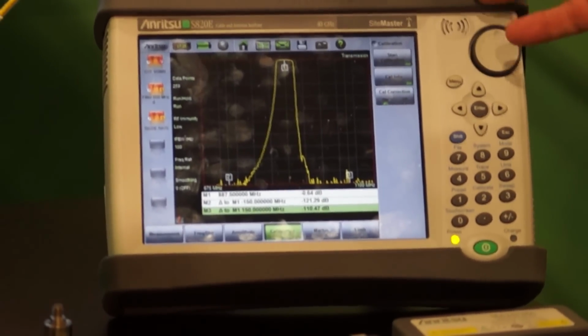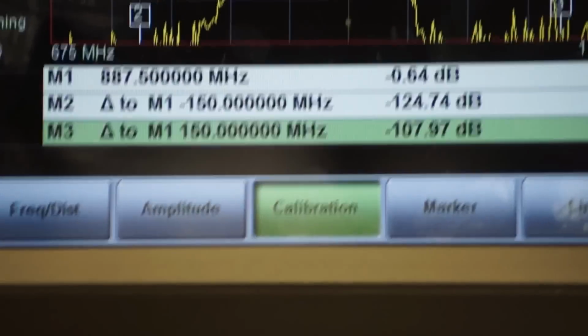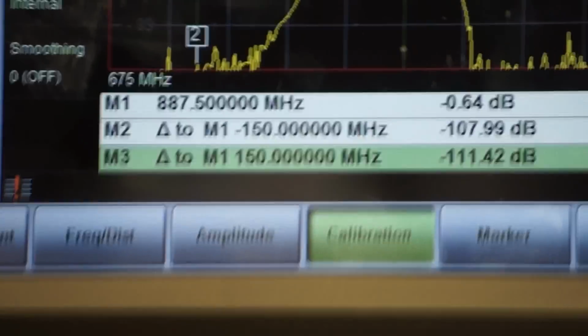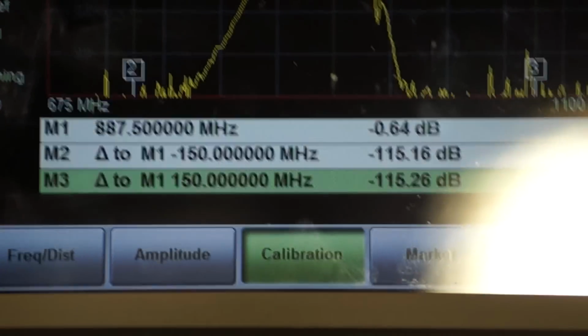What we're showing here today is a measurement on a bandpass filter. We're showcasing the high dynamic range capability of this instrument. With these marker readings at 120, 115 dB down from the center, this is dynamic range performance that was only available in benchtop units not very long ago.